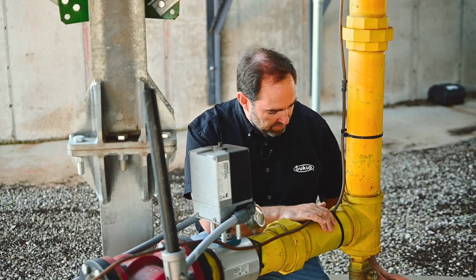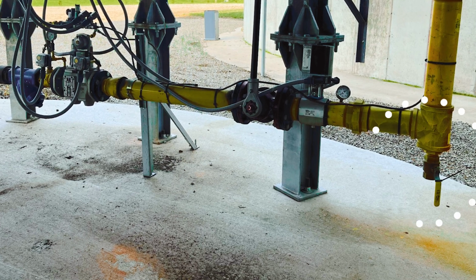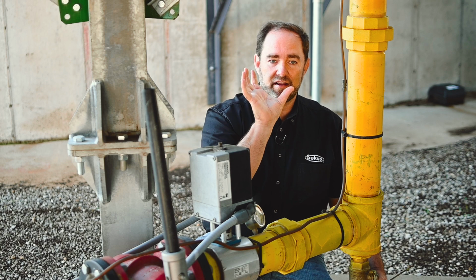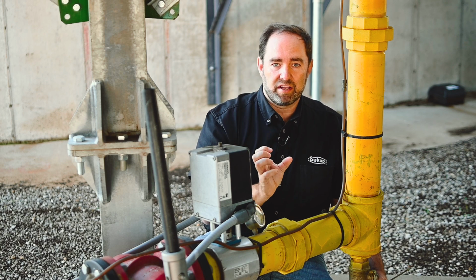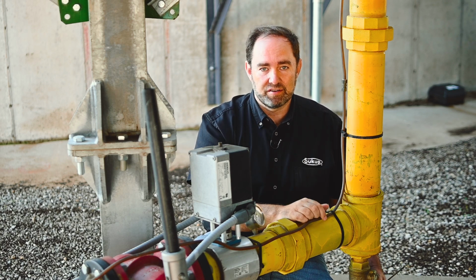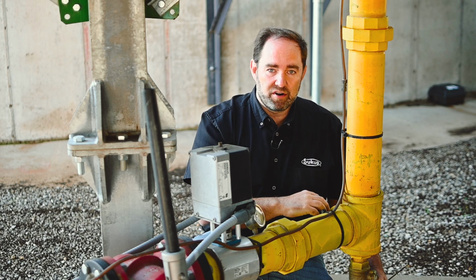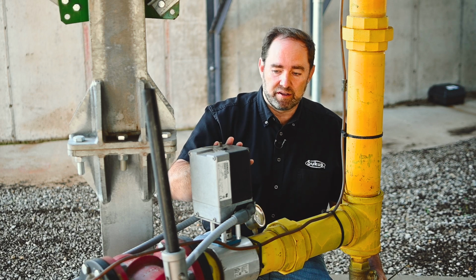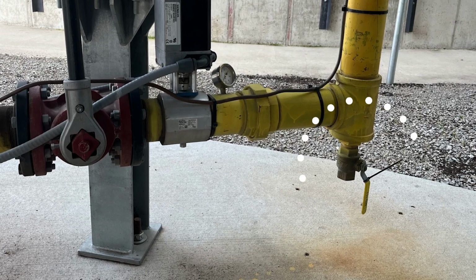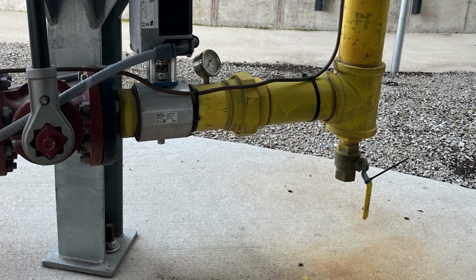On the bottom of the T, there's a quarter turn shutoff valve here. And this is very important. This is just a drain valve. So the heater is pointing up and it's kind of like a funnel. So in the off season, water can get in it, or we can have condensation on the long steel pipe. And we want to wait for that water to get out so it doesn't come and destroy the components like the butterfly valve or other components upstream. So in the off season, this valve needs to be open.